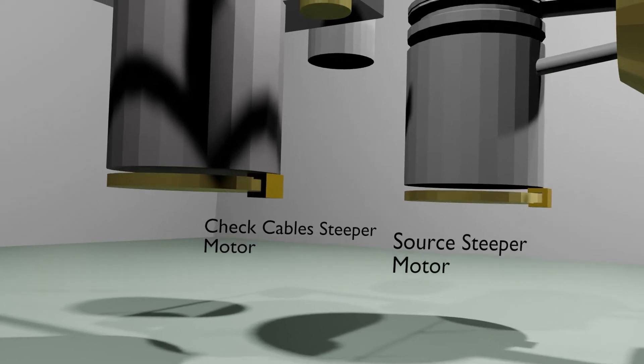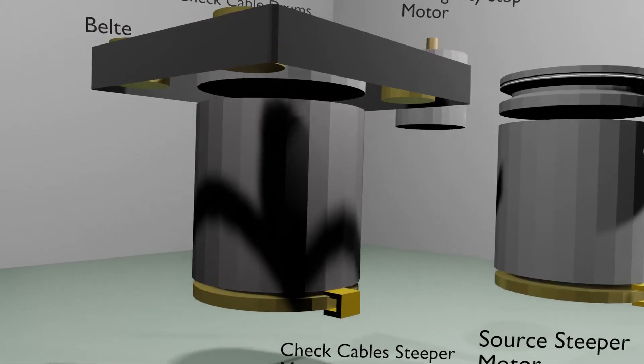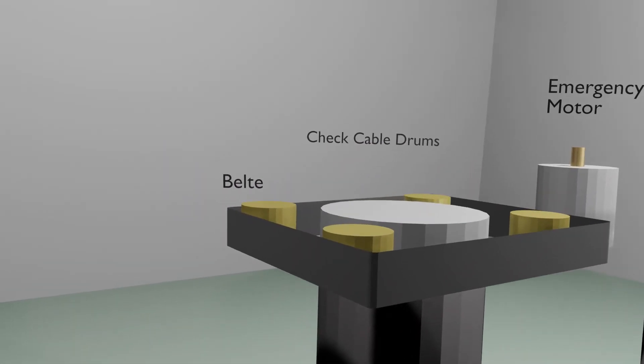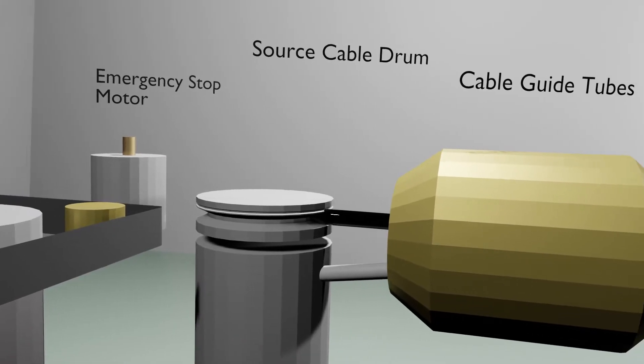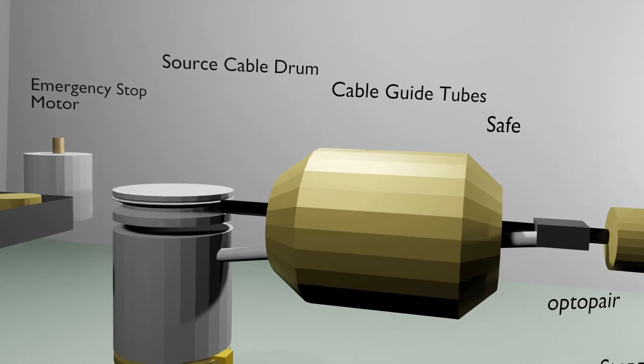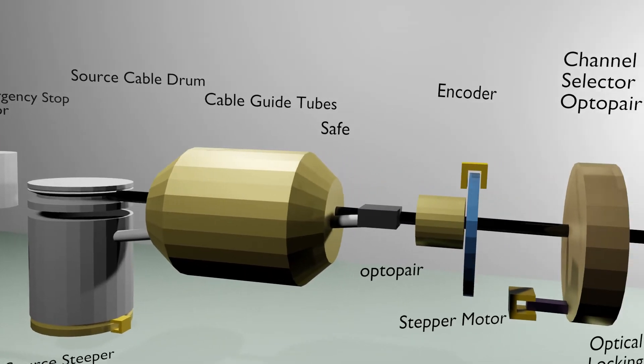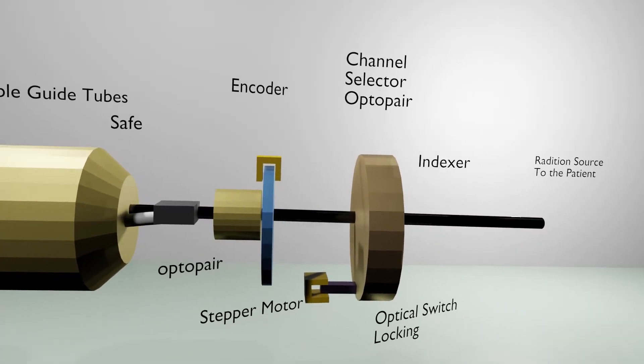The animation of guiding system for the check cable and the source cable of Nucletron microSelectron HDR device. In the off position, the source is located in the center of the tungsten safe. From there, the source can be transported through the indexer ring to the source transfer tubes and into the patient.